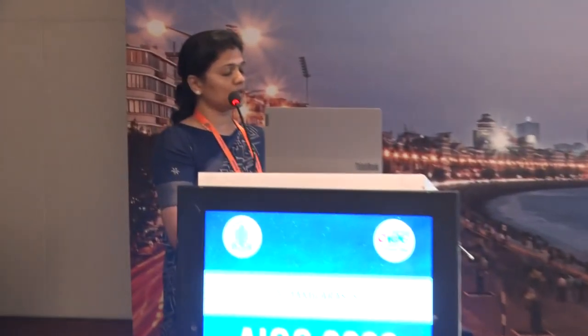And if we are using immersion, where we do not have an optical biometer, how would you go about using the latest formulae? In a few cases we have to use immersion where we are not able to measure the axial length with an optical biometer. So always when you're taking an immersion value, as I said, look for the quality of the spikes and consistency between the measurements so that the value is correct.